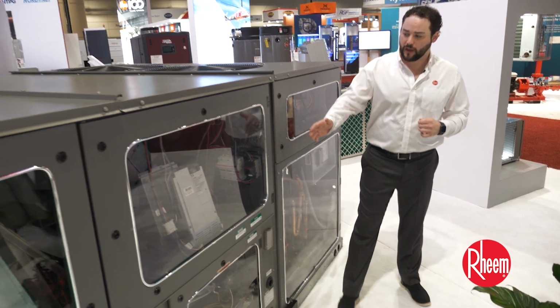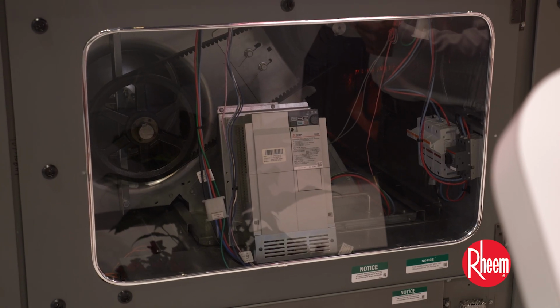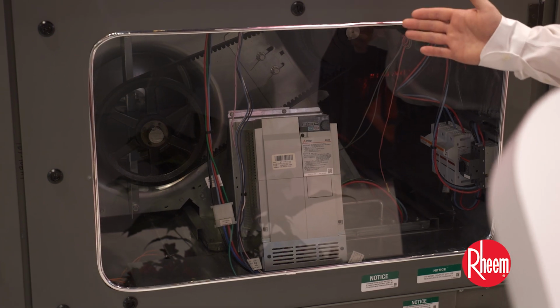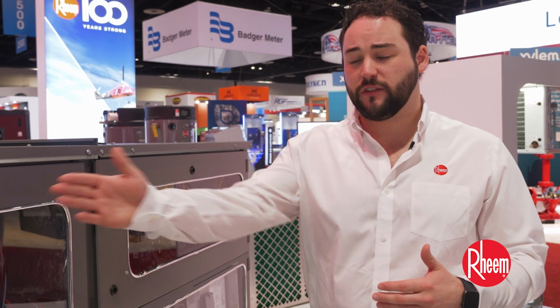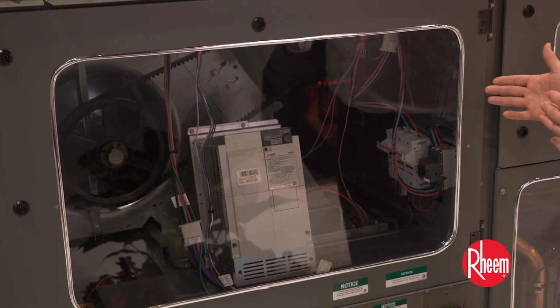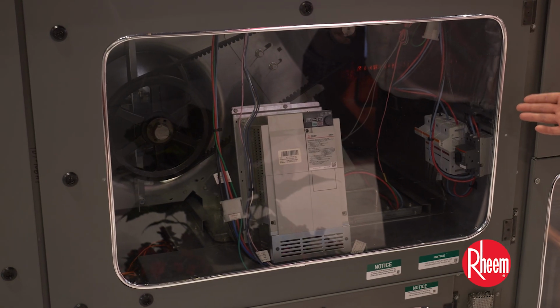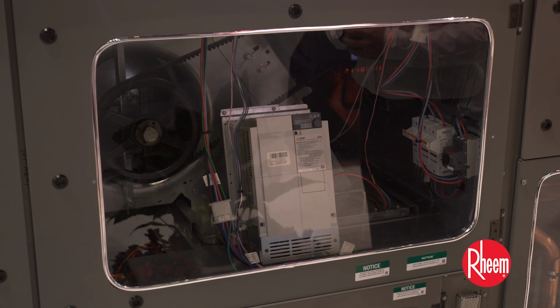Moving over here to the fan section, another one of our +1 service features is our quick slide fan rack here. They're able to pull the entire fan assembly out, service the fan, the belts, the sheaves, the motor, as well as the TXV for the refrigerant circuit without having to take out a large fan assembly and other heavy, strenuous objects built into the cabinet.